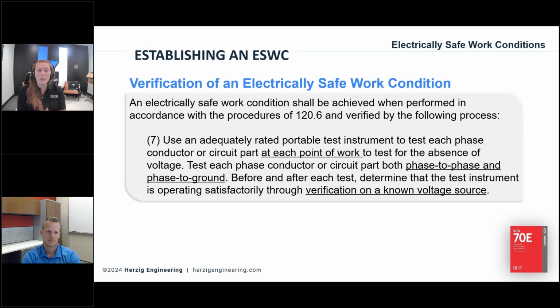Use an adequately rated portable test instrument to test each phase conductor or circuit part at each point of work to test for the absence of voltage. That is a change in the 2024 edition of 70E. It's specified at each point of work. I think it was more just a clarification. That's always what was meant, I believe.